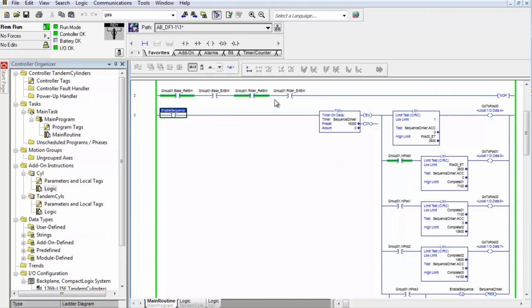You would not be doing this, what we're doing right here, at the point where you're actually using the add-on instruction. We're still troubleshooting and commissioning really the class of objects. We're doing it by putting it in code to test it. You have to put it in code in order to test it. So I'm not going to wrap this up with a real nice, neat, and tidy demonstration. I suppose that I could, since it's in position 0 right now, operate the switches while you watch the in positions and the lights.